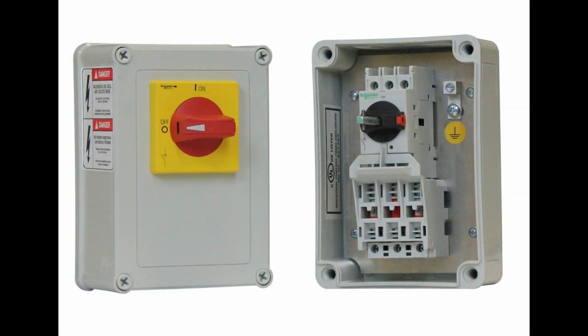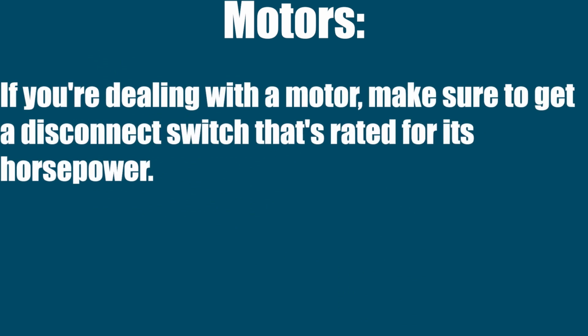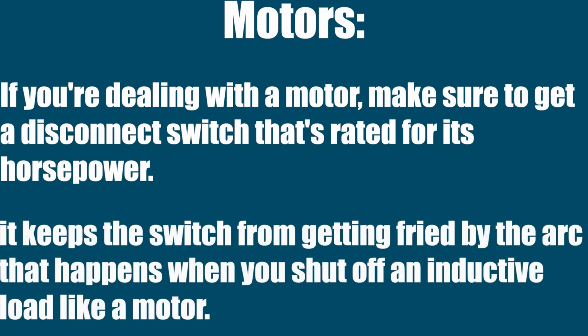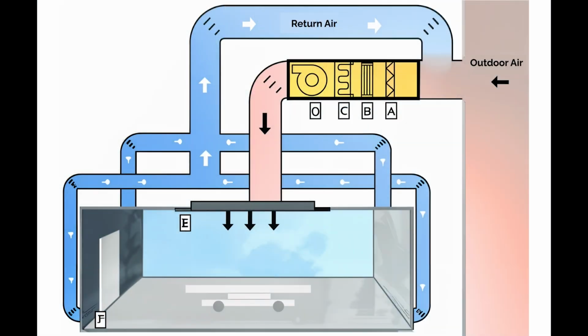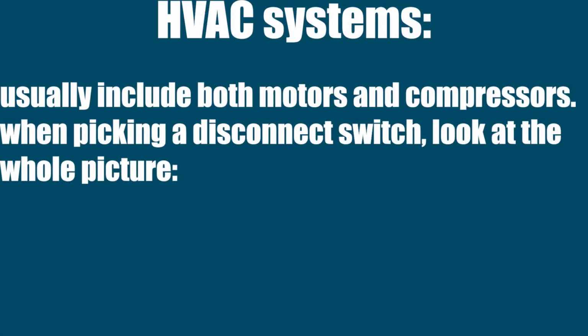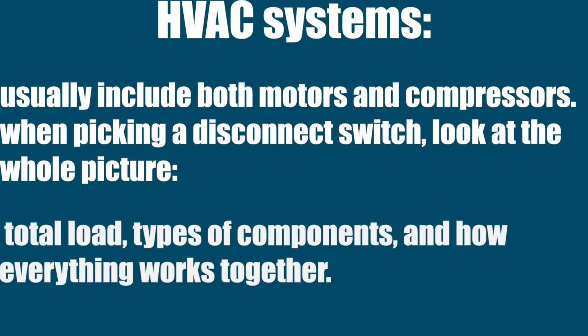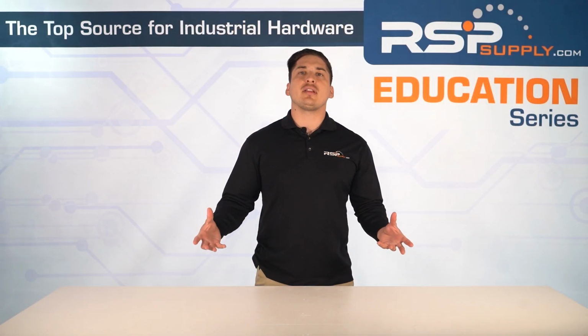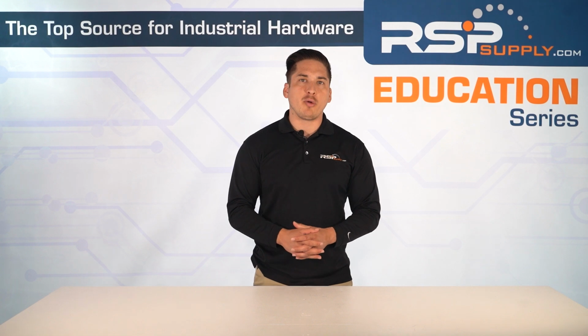Motors need disconnect switches rated for horsepower. Specifically, if you're dealing with a motor, make sure to get a disconnect switch that's rated for its horsepower. This isn't just a suggestion, it's what keeps the switch from getting fried by the arc that happens when you shut off an inductive load like a motor. With HVAC systems, they use a mix of loads together. They're a bit more of a combo. They use both motors and compressors. So when you're picking a disconnect switch, look at the whole picture. Total load, types of components, and how everything works together. These systems often need multi-pole disconnects and weatherproof housings.